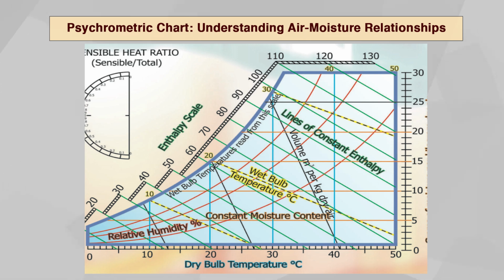Here is the basic process. First, identify two known properties. For example, you might know the dry bulb temperature and the wet bulb temperature of the air. Second, locate the intersection point. Find the point on the chart where the dry bulb temperature line and wet bulb temperature line meet. Third, read other properties.